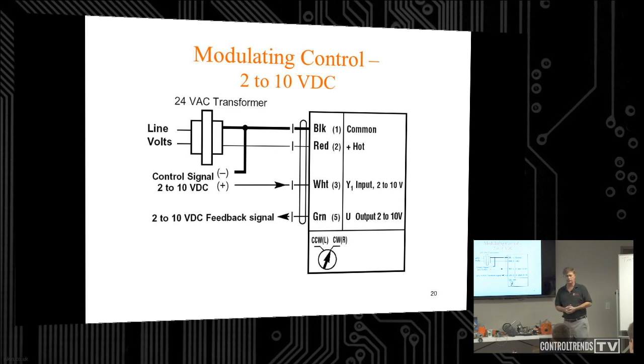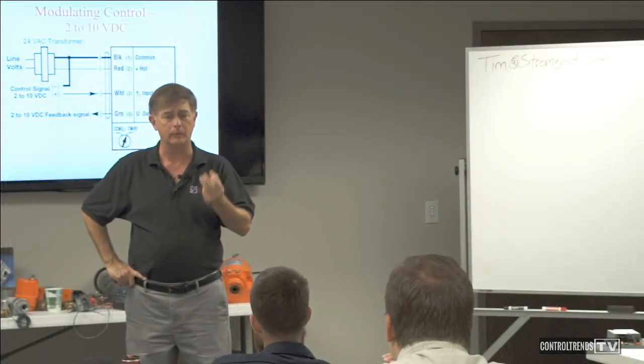Here's 2 to 10 volt DC. How many control wires do we have? It kind of depends on if we have feedback—let's ignore the feedback for a minute. How many control wires do we have? We got 3: a COM, a hot, and a signal. This is very, very common. Between this style and the other style, I'd say 80 or 90% of your actuators will be one or the other. But they're both 3 wires, so the number of wires won't tell you what kind of signal it is. Just be careful and aware.